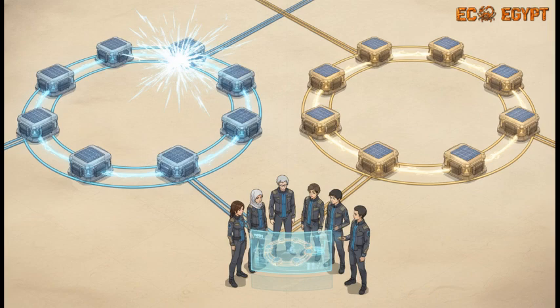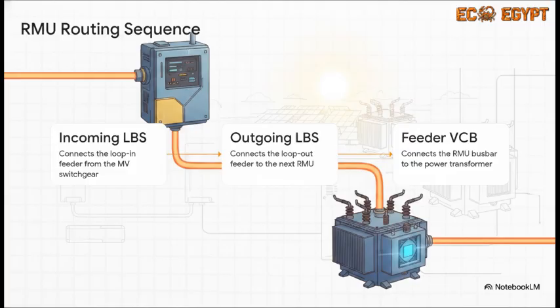Power can just be supplied in reverse through the alternate path in the loop. And to actually make those loops possible, the power inside the RMU has to follow a very strict routing sequence. First, it enters via the incoming load break switch, that's LBS1. Once it hits the RMU bus bar, the power has two options.